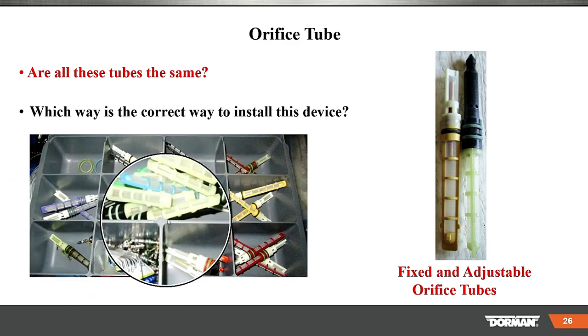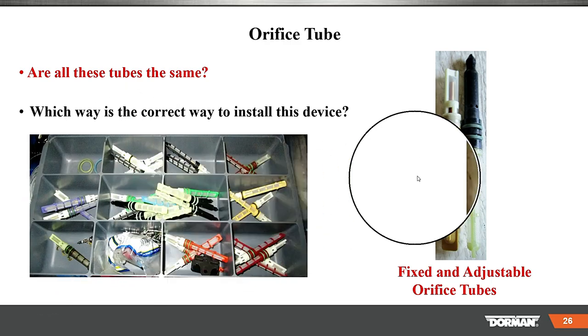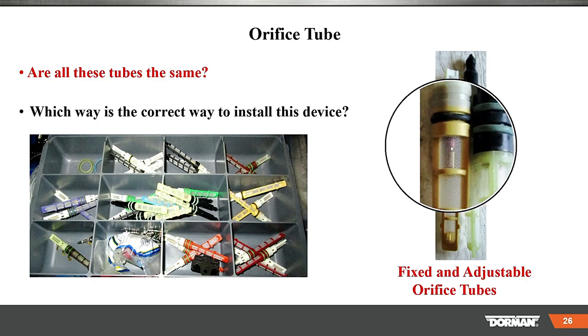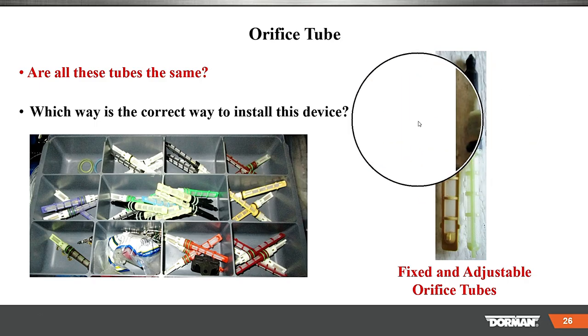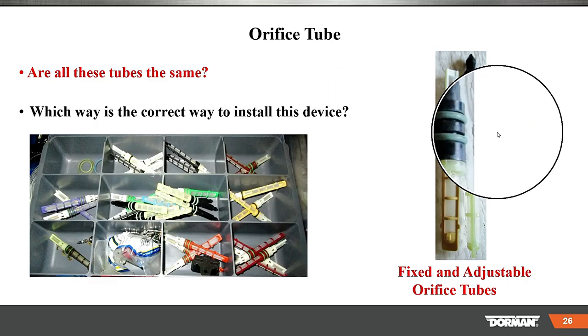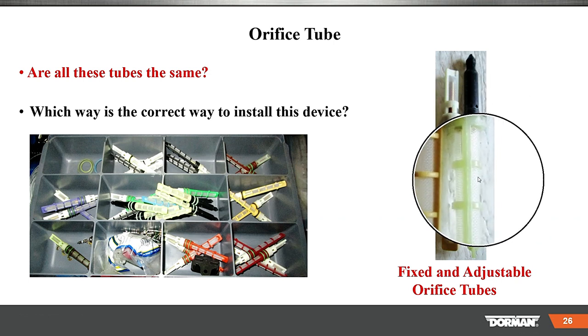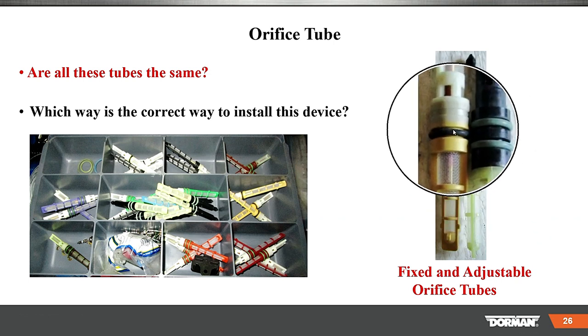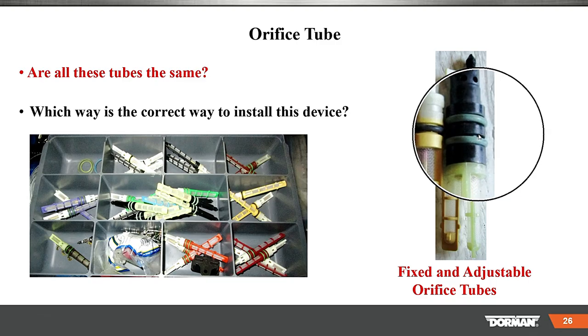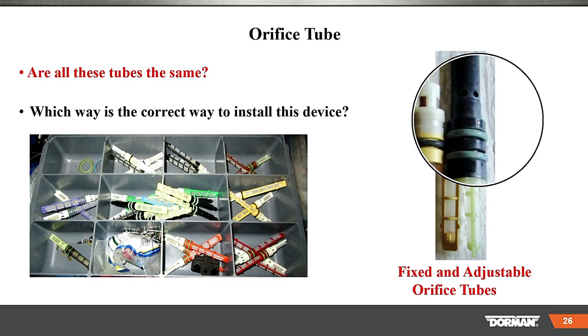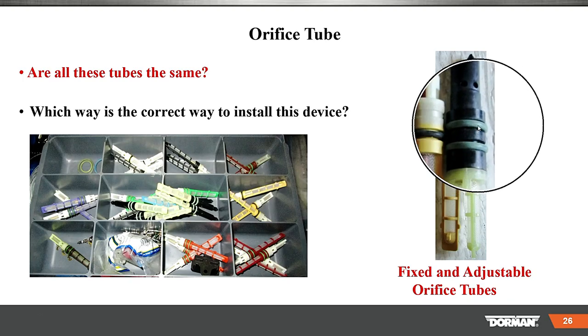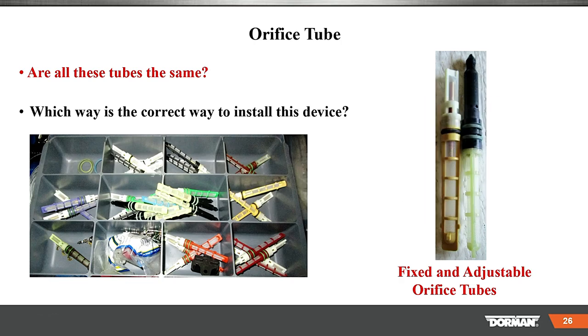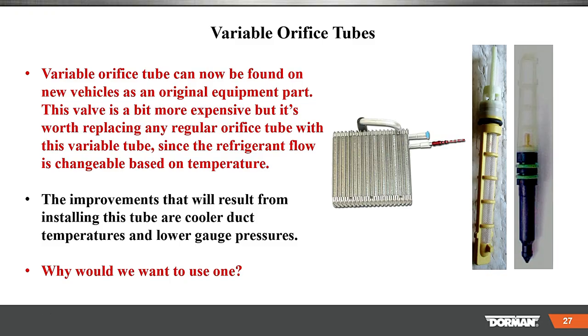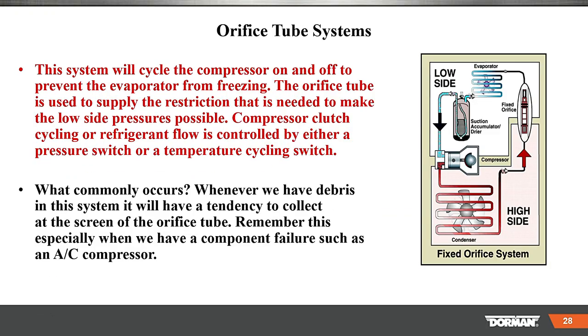These are orifice tubes or capillary tubes. You can see the one here. This is called the fixed orifice. We use these, I have all these, but I don't use them anymore. We use the variable one. By the way, there are one O-ring and two O-ring type ones. Make sure you put the right one in and face it the correct way. The variable will give you a colder temperature, okay? And there's some of that information right there.